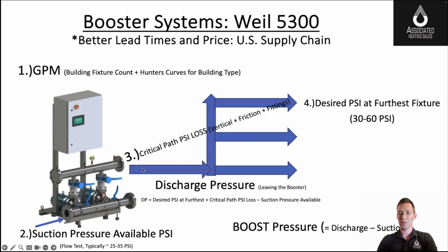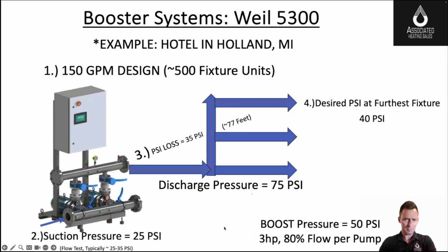The biggest thing for the engineer to figure out is how much PSI loss along the way to that furthest fixture is going to happen. And again, that's a component of that vertical, as well as the friction throughout the piping, horizontally, or the length and the fittings. And then what's my PSI that I need at the furthest fixture? There's typically flow reports from the city that tell you how much you're getting. And then we'll go ahead and determine the boost pressure. So just some numbers here that make sense, because when you go to schedule this, it'd be really nice to list out everything. That way it's very clear.